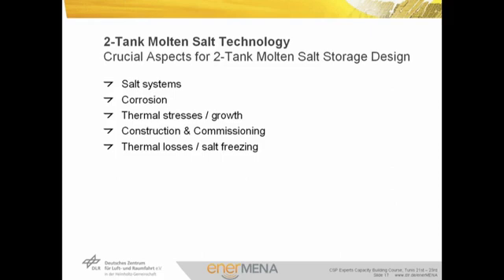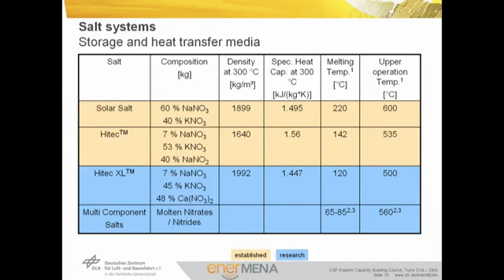Special care must be paid to the initial filling procedure. The molten salt must always be kept at temperatures above 250 degrees. Today's most popular molten salt system is a mixture of potassium nitrate and sodium nitrate. Systems using this mixture can be operated in a temperature range between 220 and 600 degrees. Another commercially available molten salt is the Hitec salt, showing a lower melting point of about 142 degrees. The maximum allowed temperature is also lower than for solar salt, and the costs for Hitec are higher. There are also other salt mixtures considered as heat transfer fluids, but usually the costs are too high for use as storage materials.